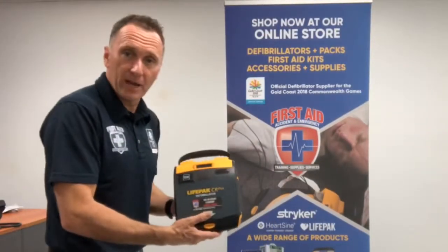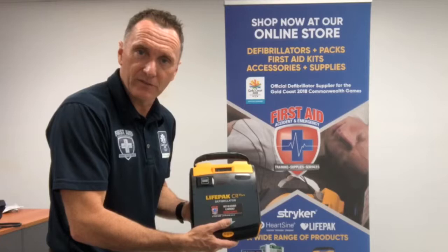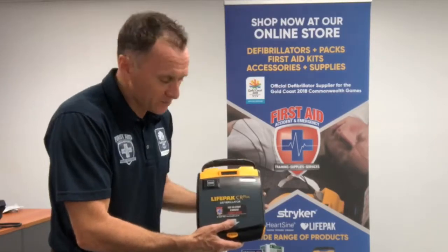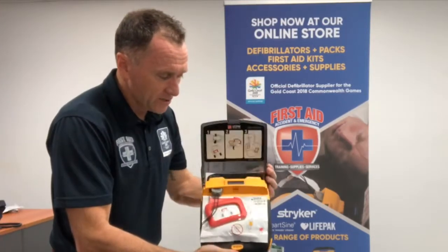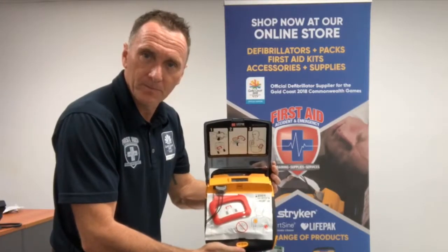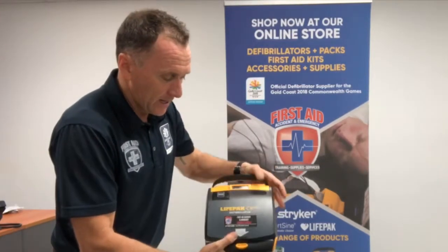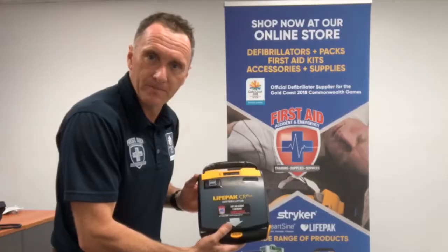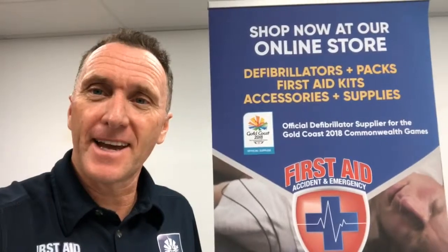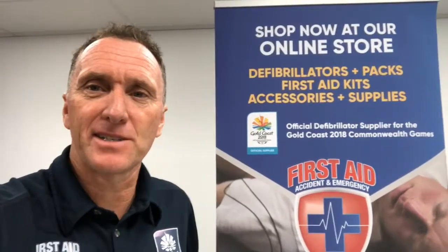Once you've changed over your new pad and battery replacement pack on the CR Plus defibrillator, we always encourage just once to open the device to ensure that it fires up. "Call for help now." And that ensures that it's now ready to go. So there you have it, changing out your pad and replacement pack for your CR Plus defibrillator.